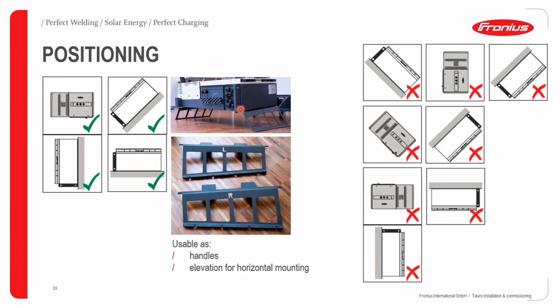So what's very important with the Tauro is that you cannot directly mount it on the floor. If it is going to be a horizontal mount on the floor, you need to provide it with these little mounting brackets. And the Tauro will basically then sit on top of these mounting brackets, and this is what we call permissible. With the handles, it's very good if you're an EPC to always have a bunch of these lying around, especially if you're going to be installing a lot of Fronius Tauro inverters. The reason for this, as I said earlier on, is that you do need to use these handles in order to make it much easier for you to mount this inverter onto its backplate.